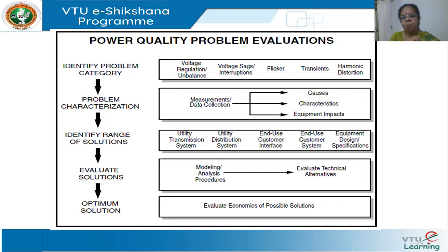Are you ready to spend some extra money to have extra reliability? So that will depend on what? That will depend on what is the cost to the consumer because of a power quality problem. Yesterday we discussed downtime costs. So what is a downtime cost? Fine, if my downtime cost is not too high, but my equipment cost is high, then I may prefer not to install the equipment and rather face the downtime cost. Clear? So this economic analysis has to take into account all these things.